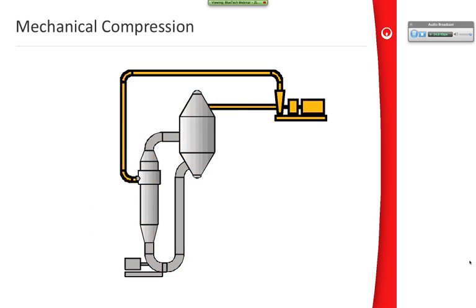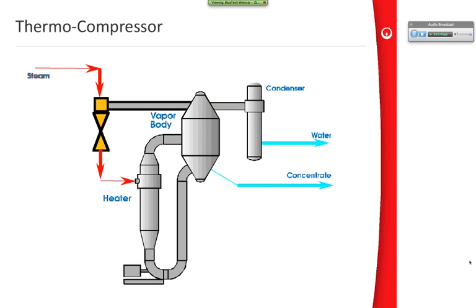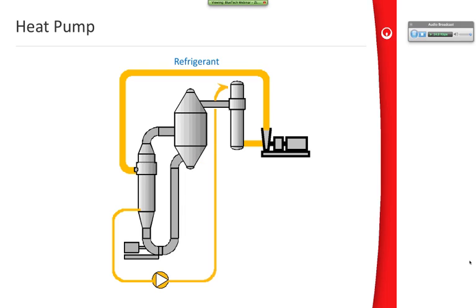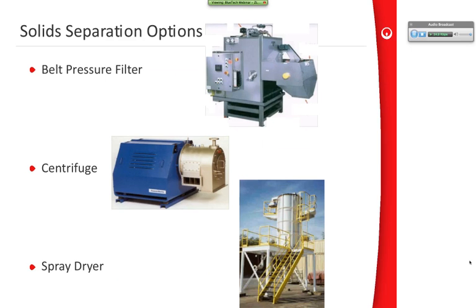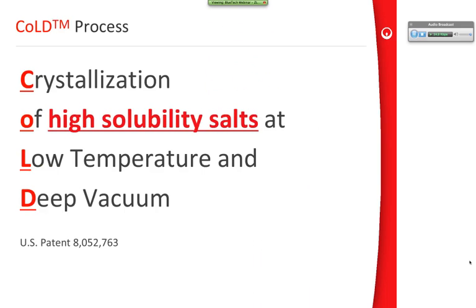We can use mechanical compression, which is sort of an open cycle heat pump. Take the vapor and compress it and reuse it as heating steam. We could use a thermal compressor, which is using high pressure steam to entrain the lower pressure steam out of the vapor body and recycle it back to the heater. We can use a direct heat pump, which uses an intermediate refrigerant liquid to transfer heat to the brine that's being evaporated. Solid separation devices: belt pressure filters, centrifuges, spray dryers, those are just some pictures of them.